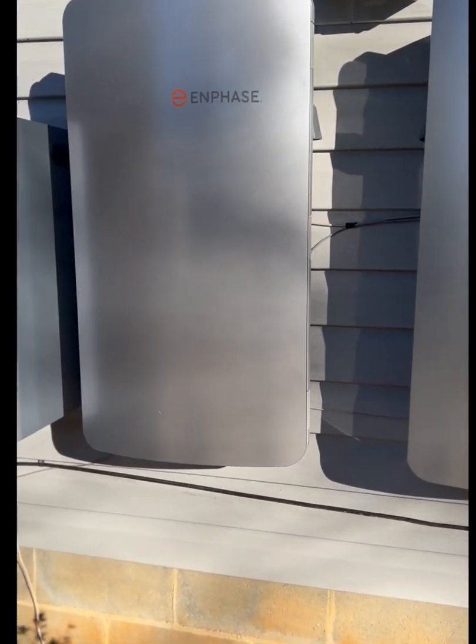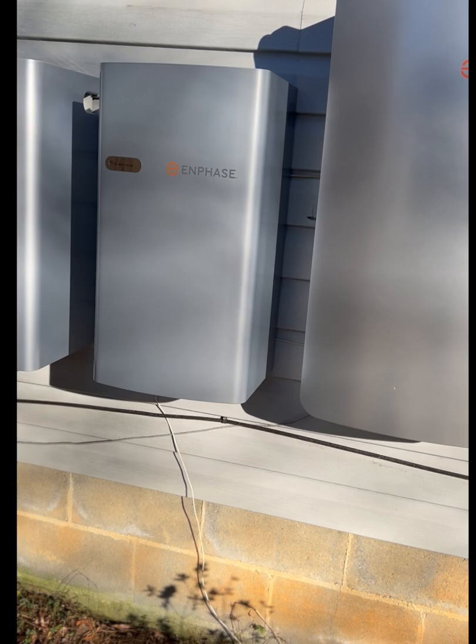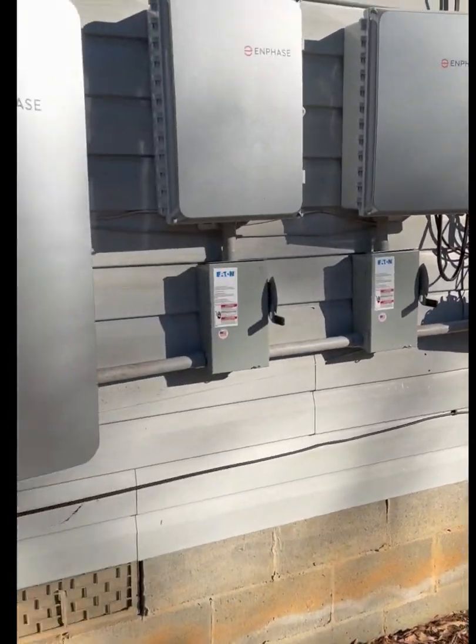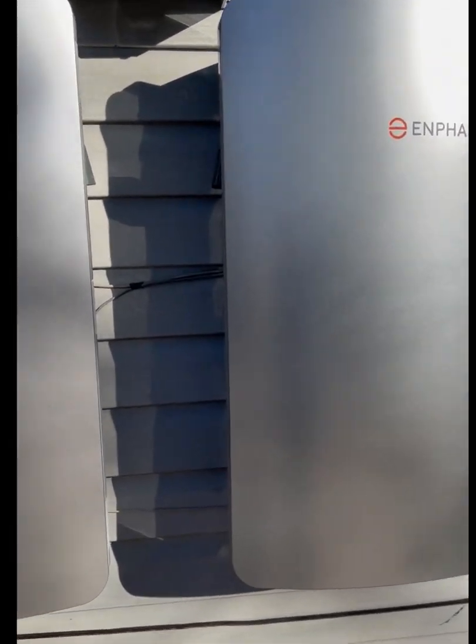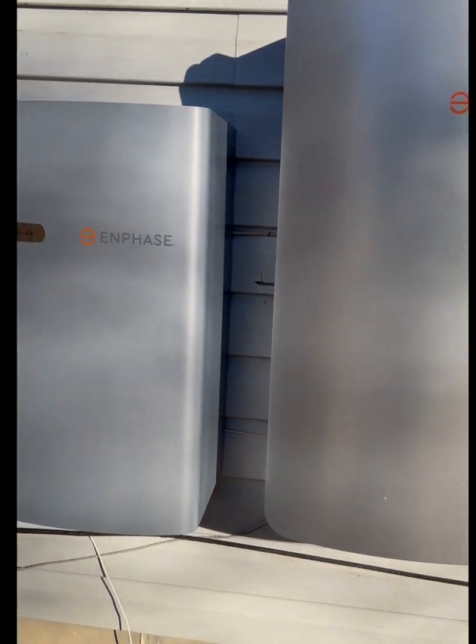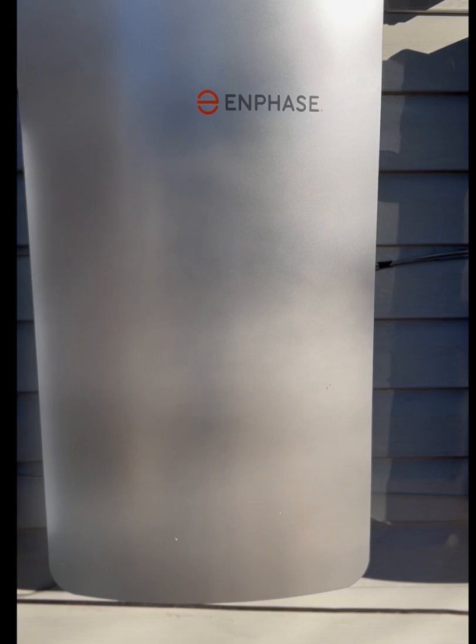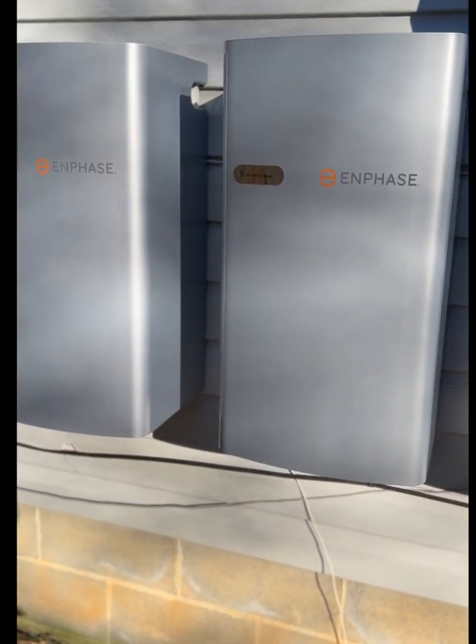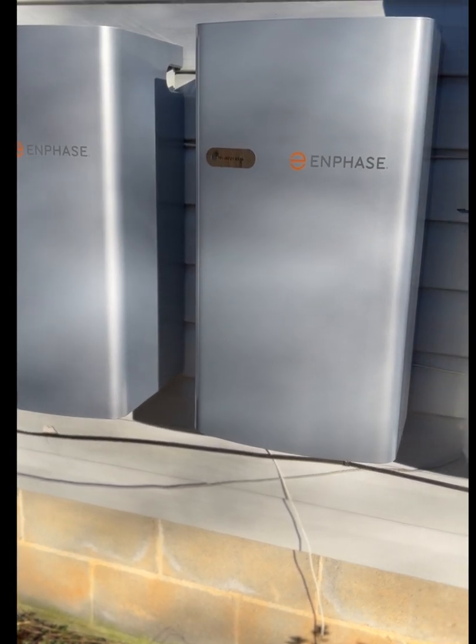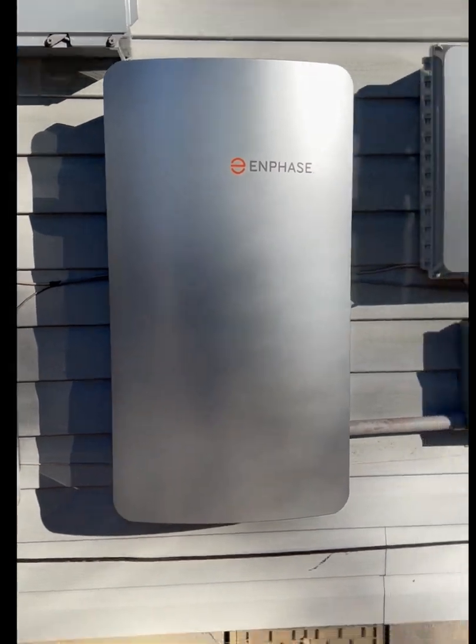They have a special relay — when it senses the power is back on from the meter, it'll switch it over and you will not only charge your batteries and power your house, but you can send power back to the grid. These Ensemble smart switches are very reliable. I've installed quite a few of these, and out of all the different systems I've done — Sonnens, Eguanas, a few different systems — these are the most reliable. They're pretty easy to commission as long as you keep your steps in order.